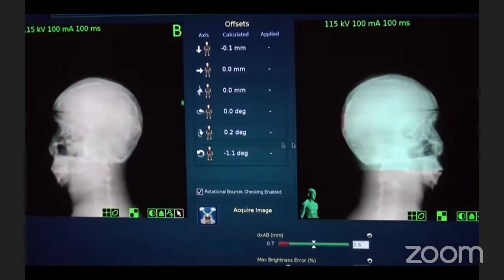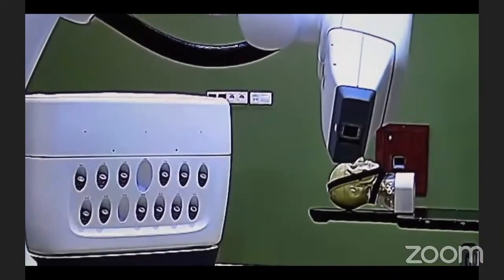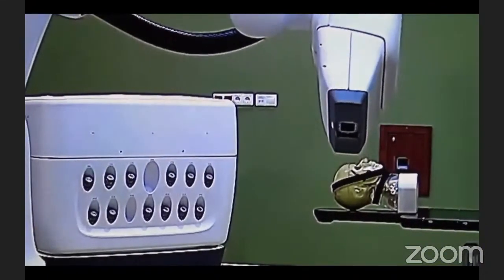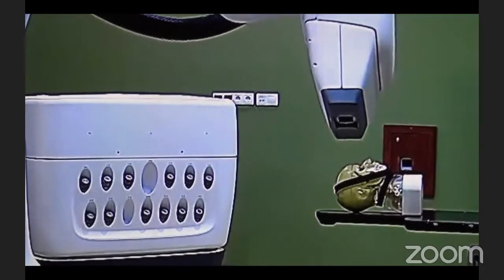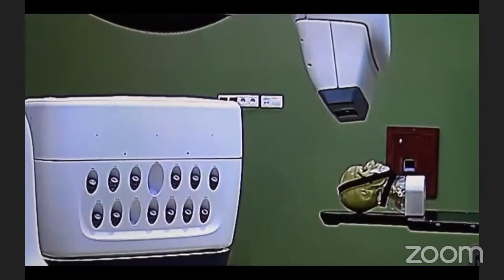The grayscale images are the expected position of the couch and the phantom. The blue scale images are the live position of the phantom. And this is the calculated offsets which will be corrected by the robot. If the position is correct, we deliver the treatment on the phantom. During these tests, all the fields are delivered one by one, just like in the case of a real treatment.